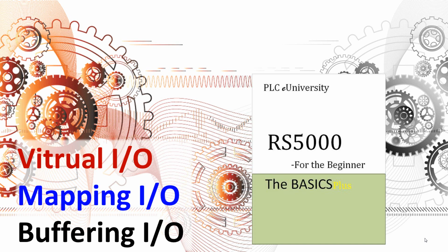Three completely different things. Virtual I/O is just creating a user-defined data type that looks like a module-defined data type. Mapping I/O is actually taking, for the most part, scattered inputs and outputs and mapping them into a common module-defined looking tag structure. So let's say that you had 3 inputs available from one card and 2 from another, and then 1 from yet a third input card.